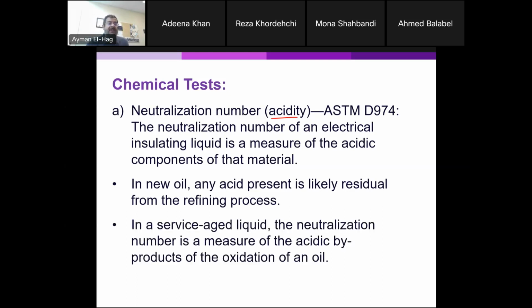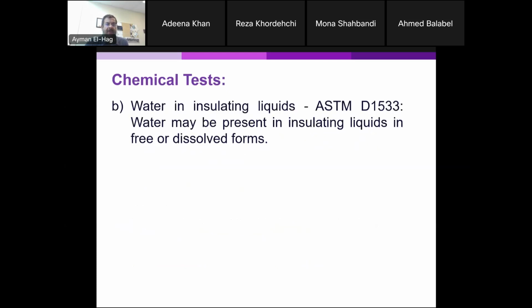However, in service, this neutralization number is a measure of the acidic byproducts of the oxidation of the oil. And as I said before, there are chemical reactions there. It is oil under high voltage, thermal stress, electrical stress, and some arcing happens inside the transformer oil. So oxidation will happen, and the higher the neutralization number, the more oxidation is happening inside the transformer oil.